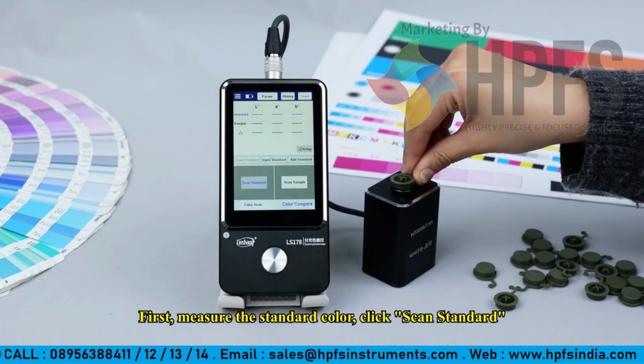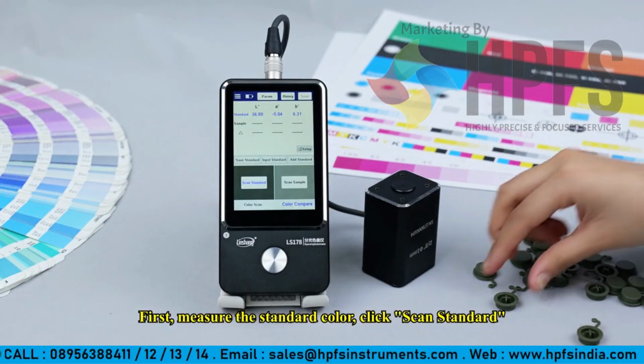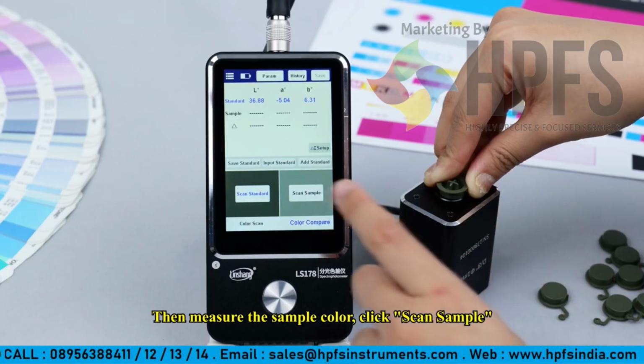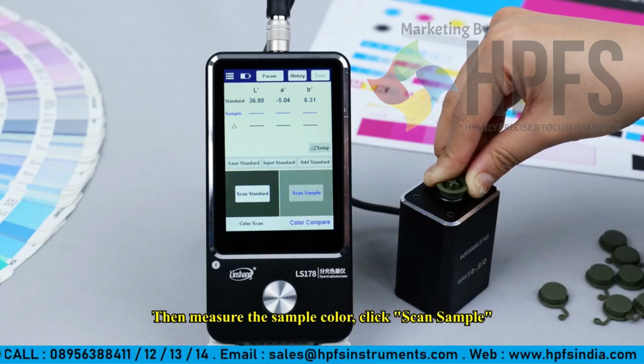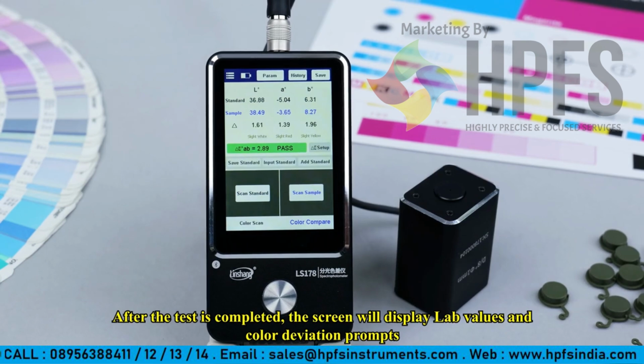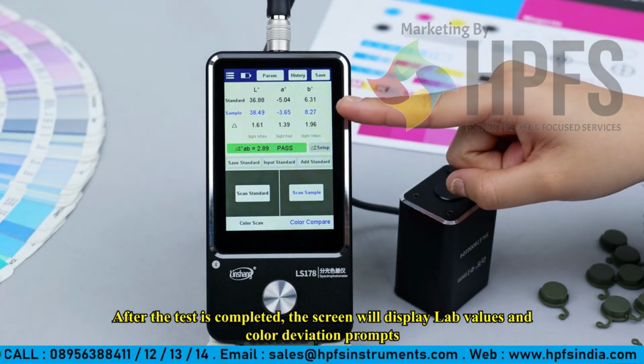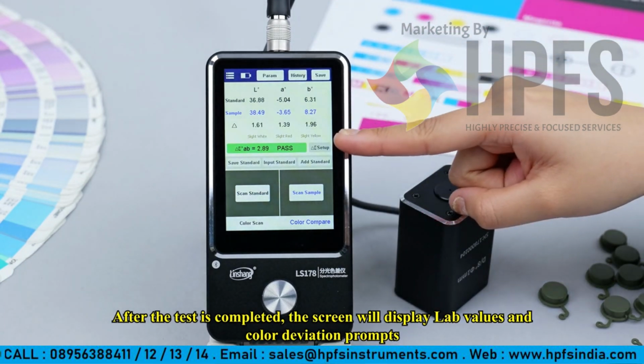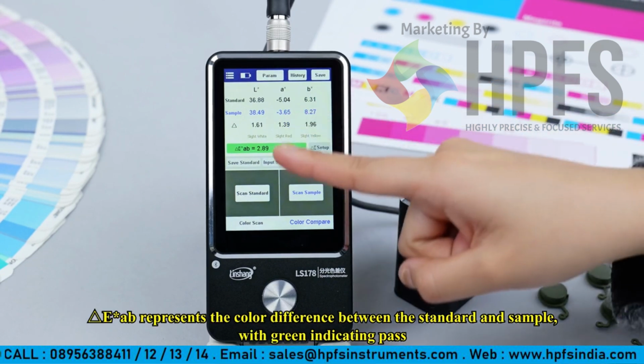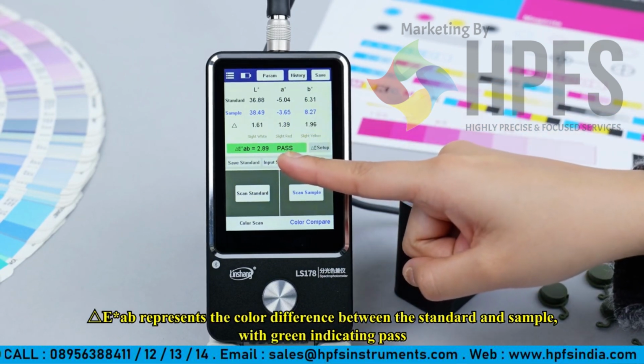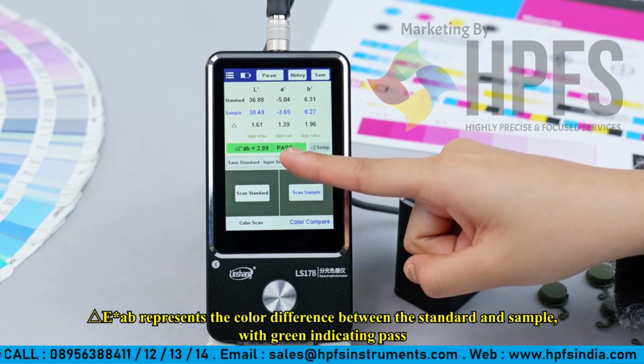First, measure the standard color, click Scan Standard. Then measure the sample color, click Scan Sample. After the test is completed, the screen will display lab values and color deviation prompts. Delta E star ab represents the color difference between the standard and sample, with green indicating pass.